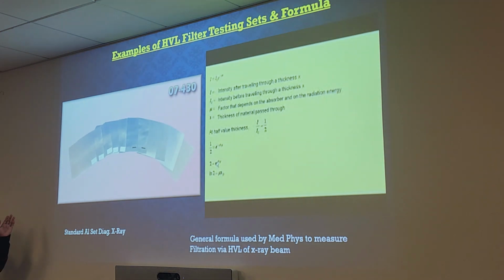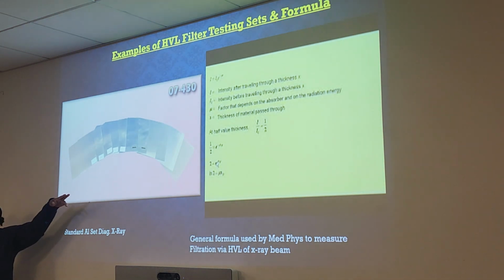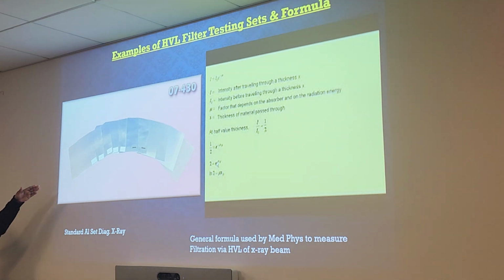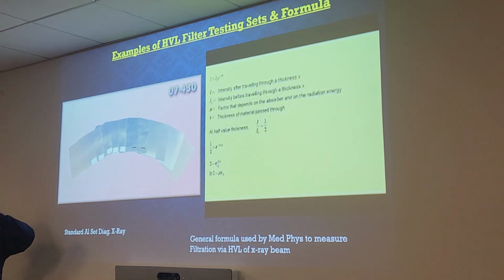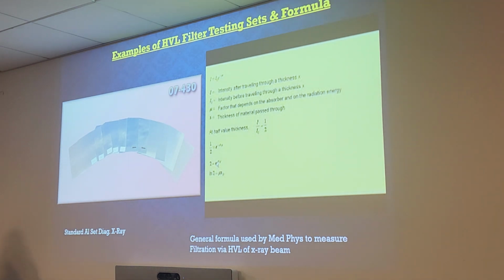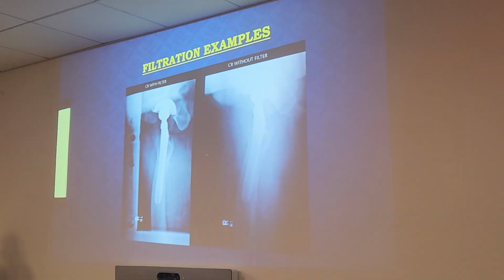So this is an example of the filtration sets that they would use. This is different levels of thickness of aluminum. And although it's blurry, on this side, this is kind of like a general formula that the medical physicists would use. There are set numbers that they already have in place from the time the machine was installed, or if it was majorly repaired, and they will use those numbers to plug into the formula. And no, y'all don't have to know this. That's just FYI. Just background information.